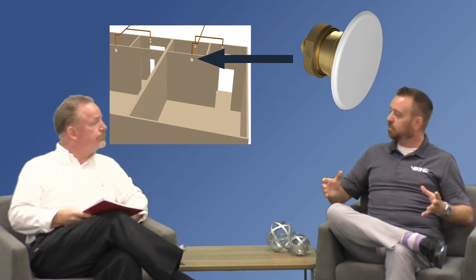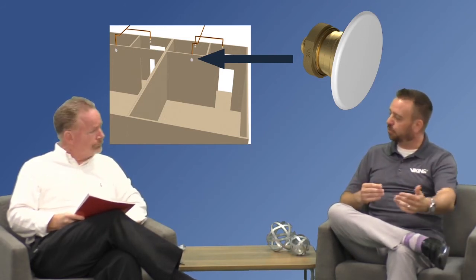And the question, what they're asking with the pendants is, yeah, they would need two because 20 by 20 is the maximum coverage area you can get for your 400 square feet. So you're never able to exceed that with a pendant sprinkler. However, with the sidewall, as I had explained earlier, you're able to manipulate the width and the throw to be able to get different coverage areas for the width and the throw area there. So we would have a sidewall sprinkler that's available for that.